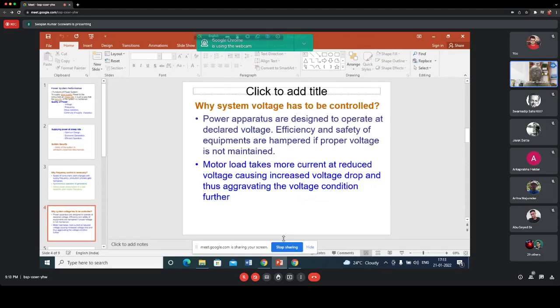And motor loads are known as constant power type of load. Constant power type of load means if the voltage varies, then motor loads will try to maintain constant power. Say voltage is decreasing, so what will happen? The motor load will try to maintain constant power by drawing more current. So at reduced voltage, it is drawing more current. So this more current will cause greater voltage drop in the system.